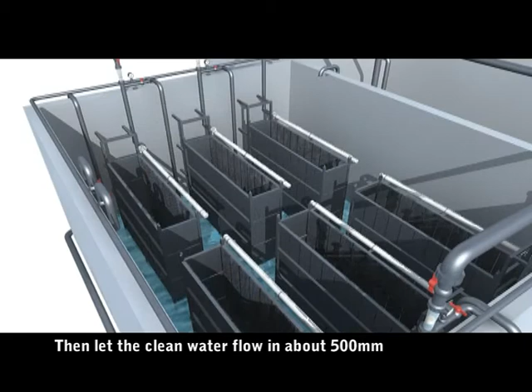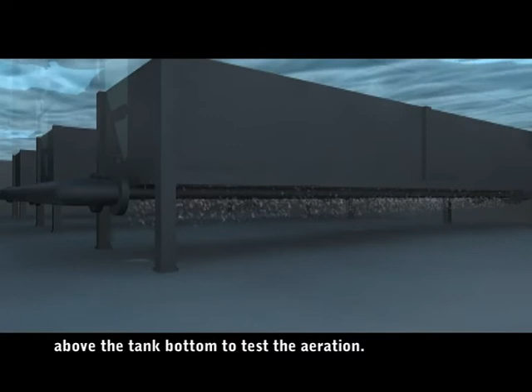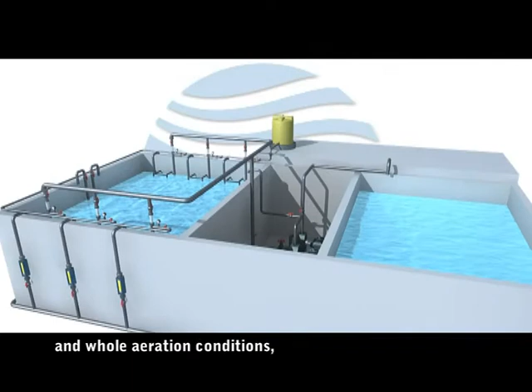Then let the clean water flow in about 500 mm above the tank bottom to test the aeration. Check whether there is air leakage or non-uniform aeration. After checking, continue releasing water into the tank until the membrane box is submerged. Then test the suction pipes and whole aeration conditions.